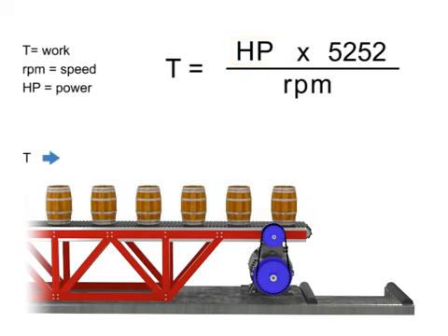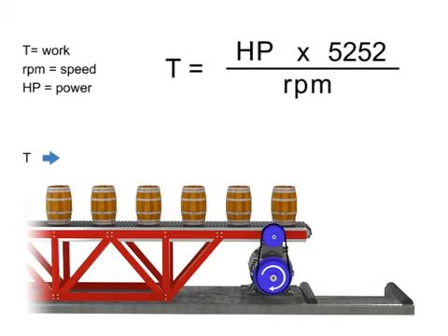Let's say we wish to keep torque constant, but want to increase the production of barrels. If the torque, or number of barrels, on the conveyor belt remains constant but speed increases, then the horsepower of the motor also increases. In other words, a more powerful motor is required to produce the same amount of torque more quickly. Similarly, the opposite is true: if we wish torque to remain constant and decrease speed, then the horsepower of the motor also decreases.